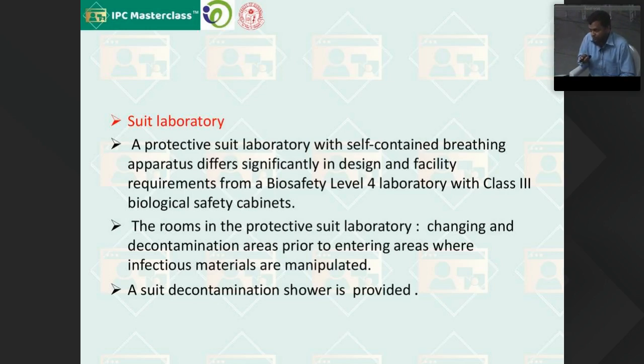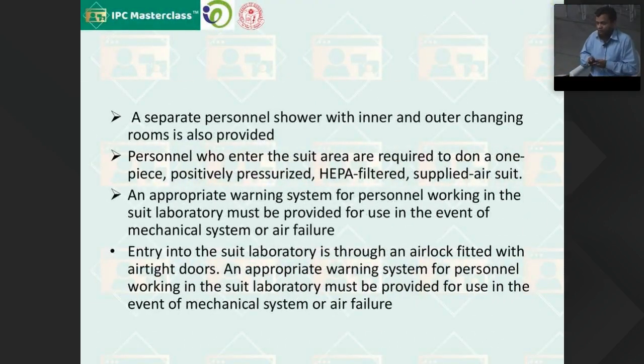The rooms in the protective suit laboratory, changing and decontamination areas, should be there prior to entering the infectious material area, and a suit decontamination shower is provided. So in a suit laboratory, the extra thing we need is a suit decontamination shower. If you see cabinet 3 in BSL-4, they require only a personal shower, but in a suit laboratory we require a decontamination shower apart from the personal shower, and there should be a separate personal shower apart from the decontamination shower for inner and outer changing. The person who enters the suit area is required to do this. This is how it differs.